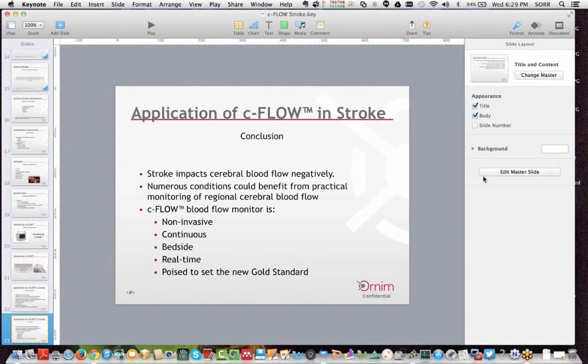So not everybody is going to be a suitable candidate for monitoring if there is a skin defect and such. In terms of staples themselves, since it's a metallic object and our device actually uses Doppler ultrasound as part of its technology, those echogenic staples theoretically could alter the signal that we get back. So we don't recommend that the device be used to monitor over staples or over brain pacemakers for that matter, or anywhere that there's a skin defect.